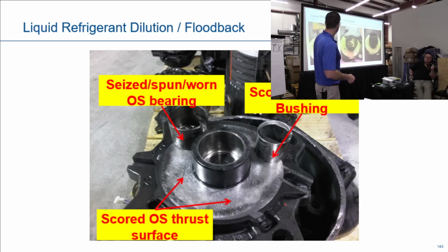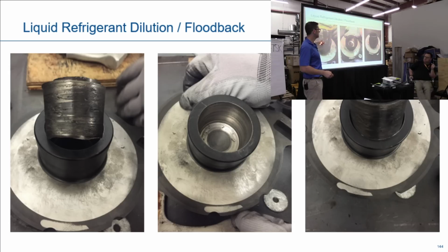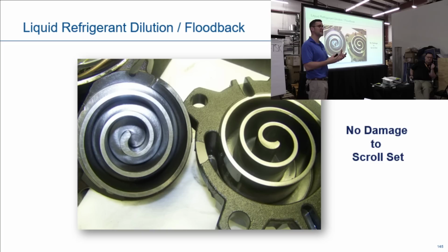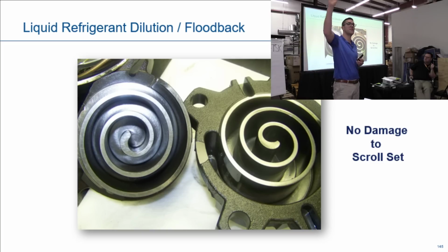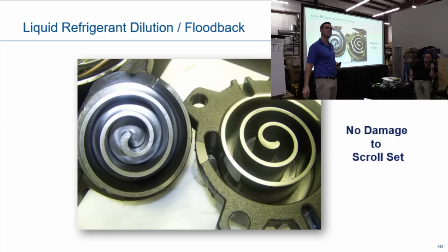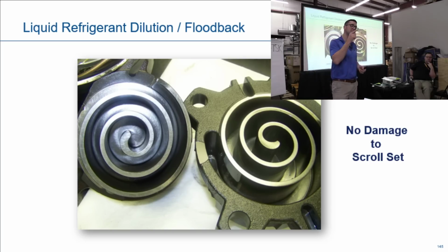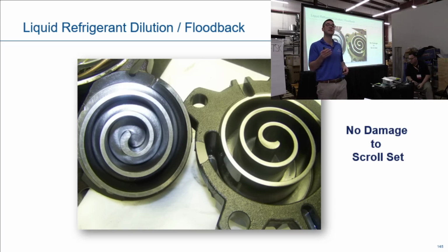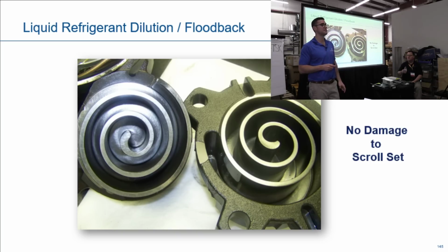Here's another picture of flood back dilution. You look inside the scroll set, there's nothing wrong with them. How many people have cut open a scroll before? Show of hands. You definitely should. If you work on scrolls all the time, take it back to your shop. If it's an out of warranty compressor, it's going back to the scrap metal place, so cut it open and look inside. Why did it fail? Because if you don't know why it failed, how long is the next one going to last? That's how important it is.